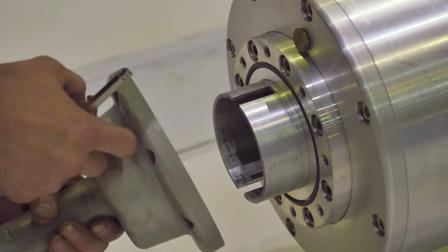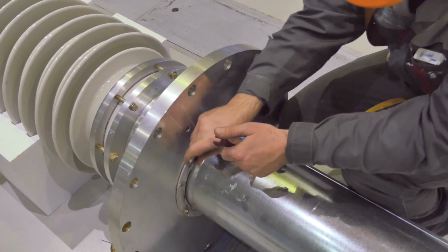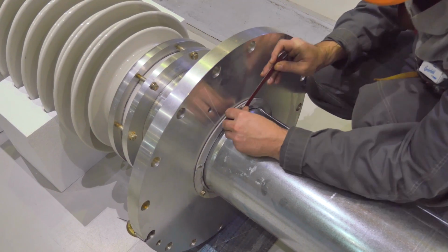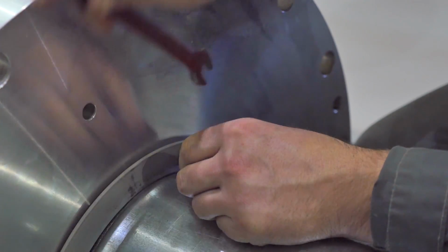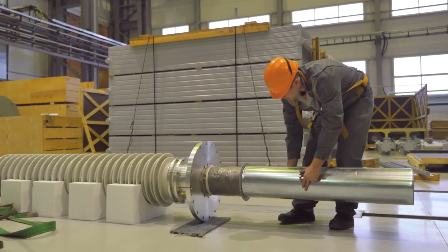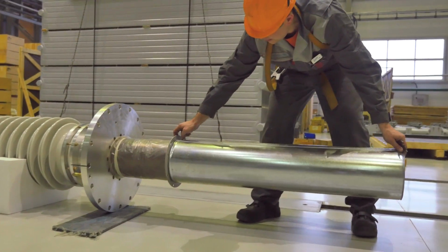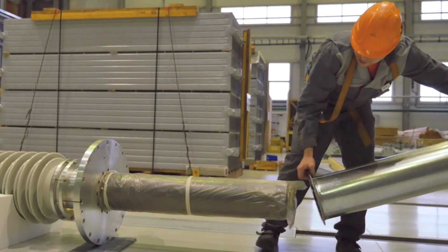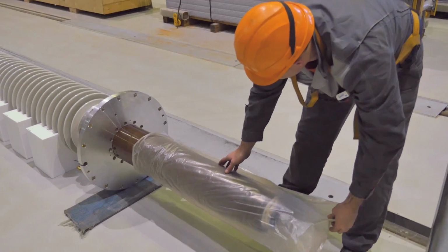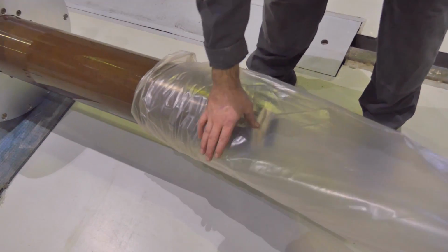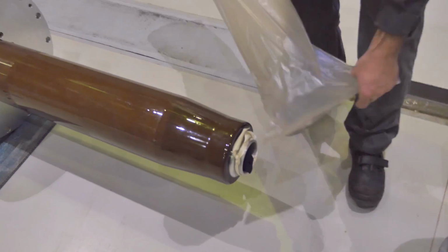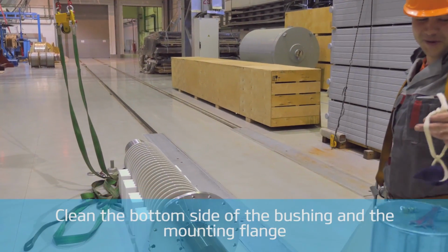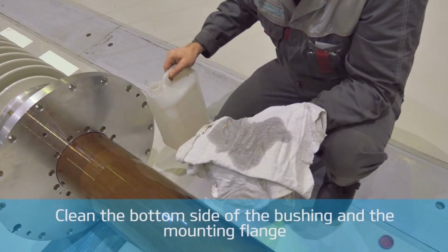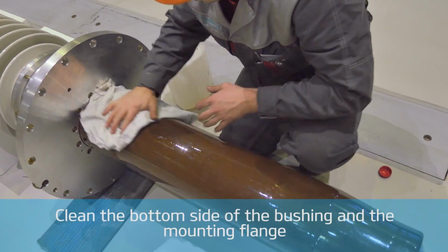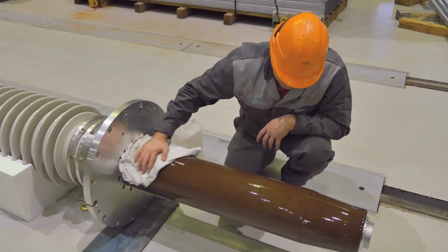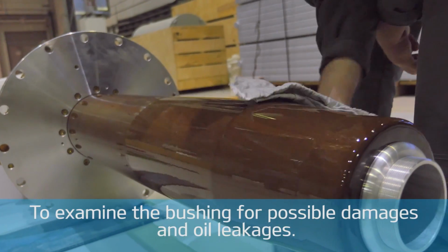This operation can be performed either on the horizontally or vertically positioned bushing after its lifting onto the temporary rack, either before removing the protective cover from the bottom side of the bushing or after that operation. If the bottom side length and dimensions allow, the cover can be removed by one technician. Remember to clean the bottom side of the bushing and the mounting flange exactly as with the bottom terminal bushings. Likewise, do not forget to examine the bushing for possible damages and oil leakages.